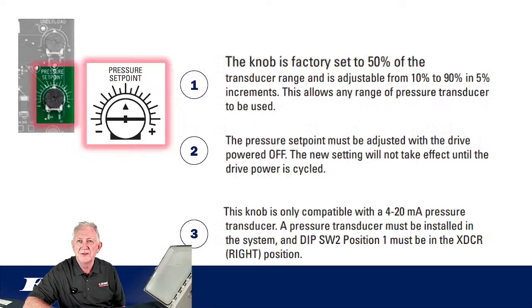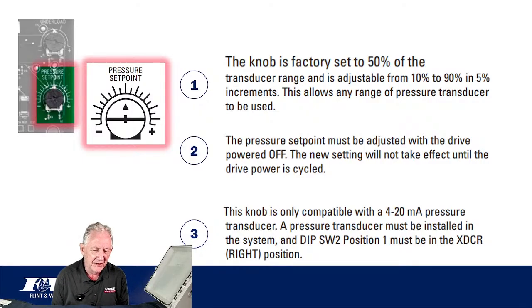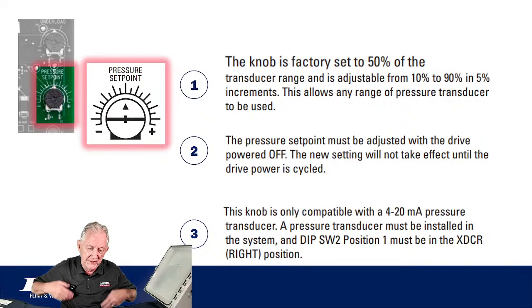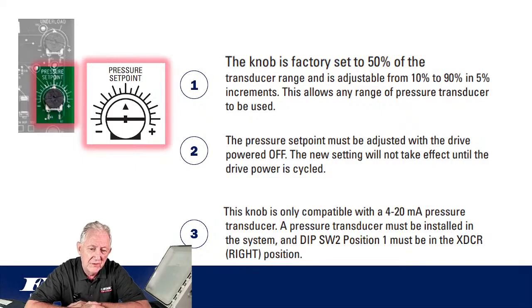I want to talk about this pressure set point. Particularly if this is being used with a pressure transducer, I'm going to read this to you. It says, the knob is factory set to 50% of the transducer range. Stop. Transducer range, what did I tell you that was? A few minutes ago, I told you that was a 100-pound transducer that we ship out of here standard with this drive.